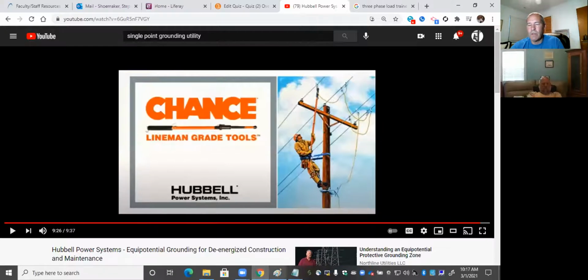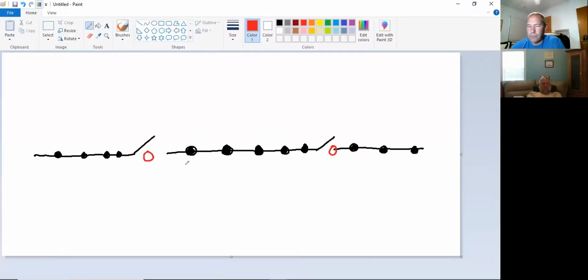A couple notes here and a couple questions for you guys. I've got an open point on the left-hand side and an open point on the right-hand side. All right, that's all I have so far. Can I work in this zone area and not have to use rubber goods or rubber gloves? No, you cannot. It is not allowed. I can have the two open switches, but I still have to use all of the safety practices as far as cover up and rubber goods as I would if I went onto an energized line.